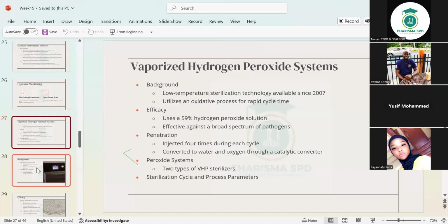All right. Sterilization cycle and process parameters are all there. The temperature, as I told you, it's around 131. So they're going to have the parameters for you there. You are not going to set it. It's going to be there for you. And especially when you process an instrument, the sticker or the label you put on comes with the parameters on it. Your name, the date and time you process it, the parameters, the name of the instrument, and the parameters on the sticker. So even if you don't know anything, look at the parameter that was printed out and then use that. Okay?